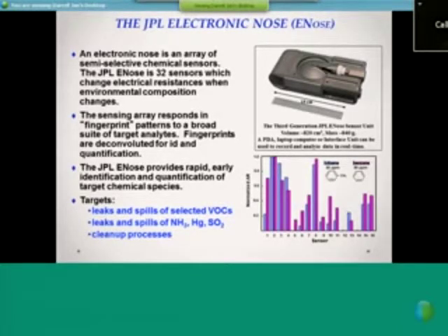and you really don't want to be in a position to have the crew nose be your only detector. Regarding biologically inspired, certainly this architecture is biologically inspired. The original concept was Nate Lewis at Caltech, and refined into quantitative form by Dr. Amy Ryan at JPL. And in fact, I mentioned there are many different polymers comprising the array of sensors. And in fact, of the one we flew, one of them did use carbon nanotubes as its conductive dopant, and the other one didn't use nanotubes, but they did use nanoscopic particles of carbon. So some of that nanotechnology research has gone into this kind of device. It is continuing, although there are budget constraints.